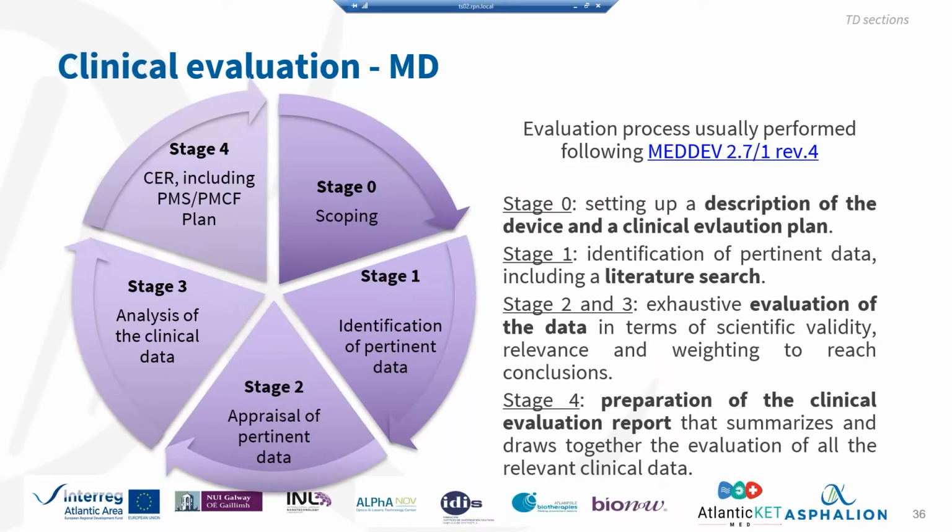So how are we going to perform this clinical evaluation? Up until now it was performed with the MedDev 2.7/1 revision 4. It's got to be said that with the regulation, the scope is even broader. So performing the clinical evaluation according to this MedDev should suffice, but it's a bit more thorough with the regulation. Let's remember that MedDev was a guidance for directives, not for the regulations.